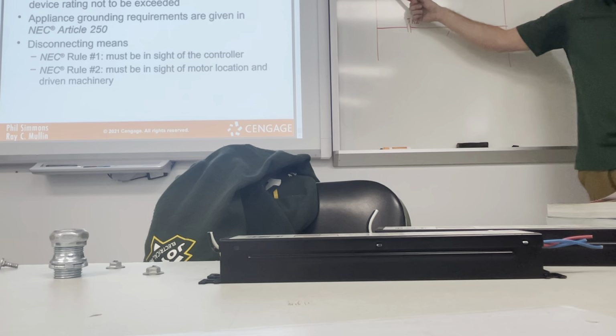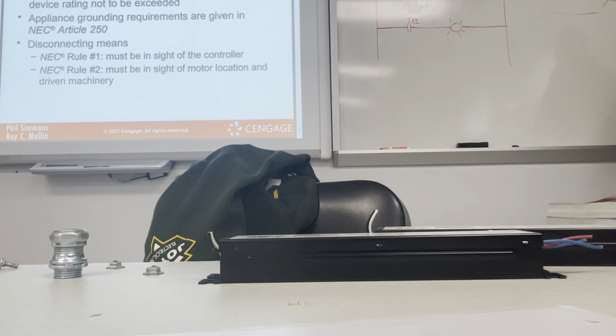That's a stop button right there. That's normally what? What position is that? What's its state? Normally open or normally closed? Closed. Why? Because it needs to be able to flow through, and then for the shut off, it needs to open up when we turn it off.